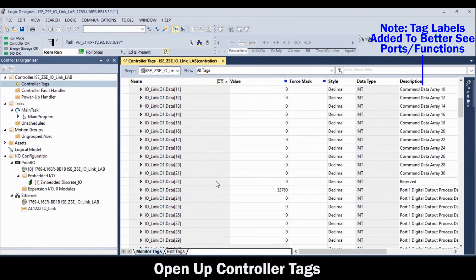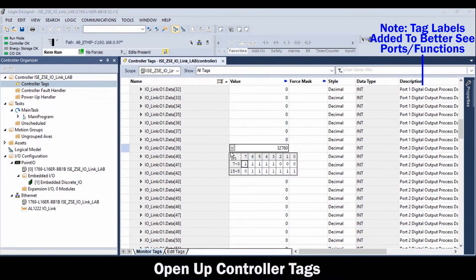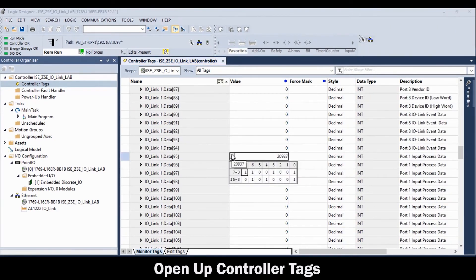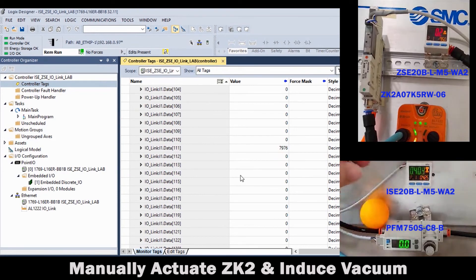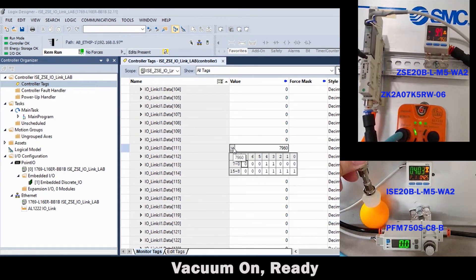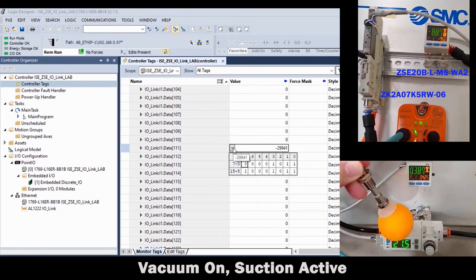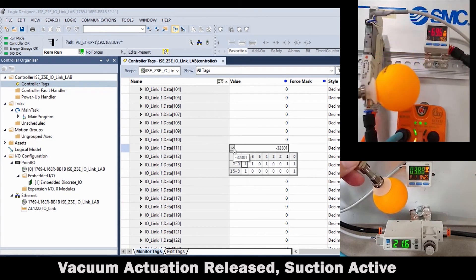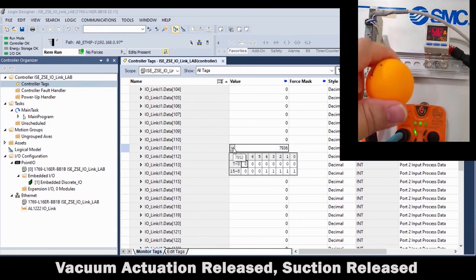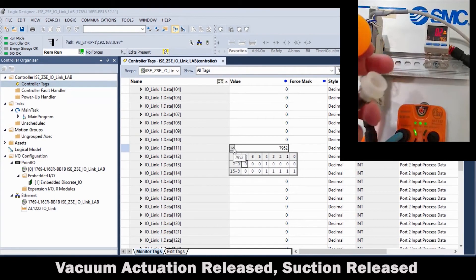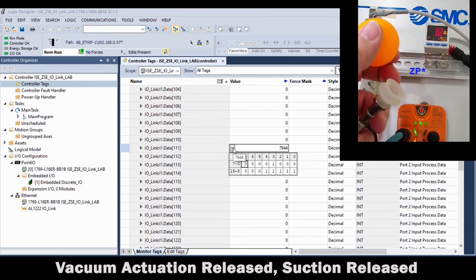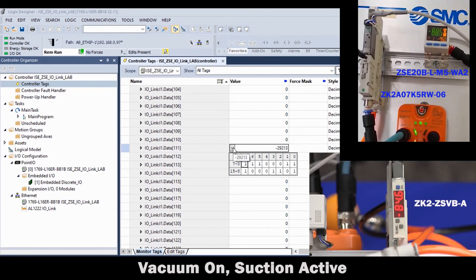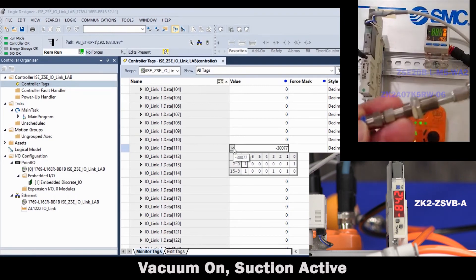Go into the controller tags. Note the tag device descriptions that were added as helpful labels for the IO-Link master port functions. Now, with pressure on through the ISE20, manually actuate the ZK2 to induce a vacuum. Verify this with the pressure cup, ping pong ball, the ZSE20 reading, and the registers in Studio 5000. Utilize the quick guide or operation manual to fine tune your application.